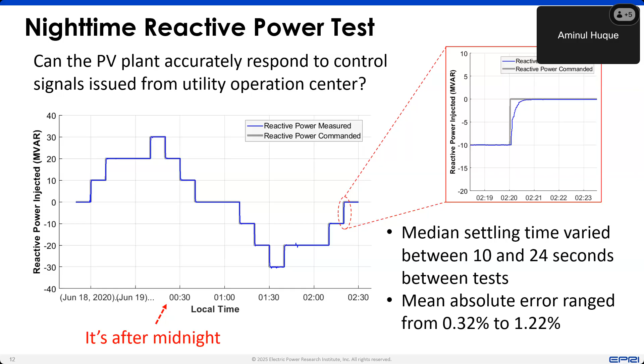Then the second question is, to keep the plant operational, how much active power is needed? For this particular project, compensation was also provided to the plant owner or plant operator for that active power consumption. But again, this is a research project, so don't tie that to a business decision here. And also, if we have an increasing amount of reactive power demand, in both absorption and injection directions, how much active power is needed? What we have seen is that if we let the plant go into sleep mode, which is the default setting, it was taking roughly 317 kilowatt. Again, this is a 90 megawatt plant. So 317 kilowatt was the demand in this traditional operation where the plant goes into sleep mode. But if we keep it operational so that we can do reactive power support, no matter whether fixed VAR or volt VAR, that's different, just to keep it operational, somewhere between 600 to 700 kilowatt was required additionally compared to the sleep mode.